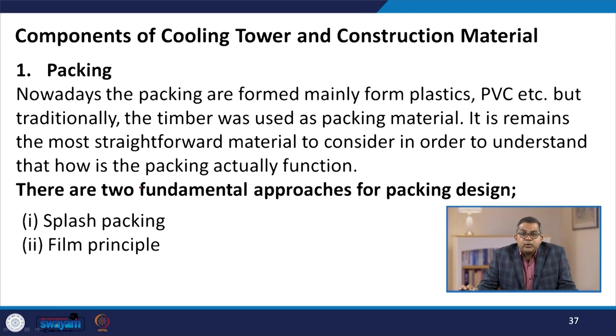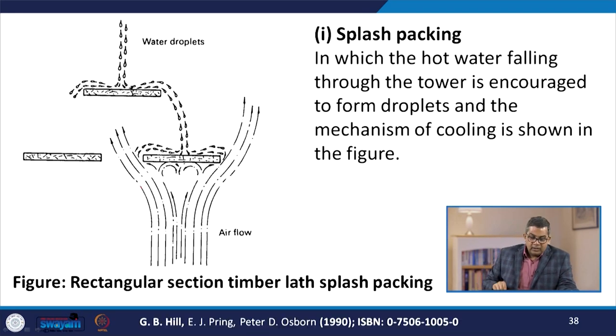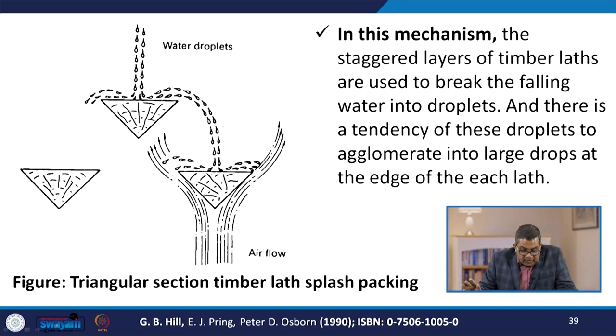Now, there are two fundamental approaches for packing design. One is the splash packing and the second is the film principle. This is the splash packing, in which the hot water falling through the tower is encouraged to form droplets, and the mechanism of cooling is represented in this particular figure. These are the water droplets, and once they are formed, the surface area enhances, thereby promoting heat transfer, and then it goes to this channel, and this is your air flow.